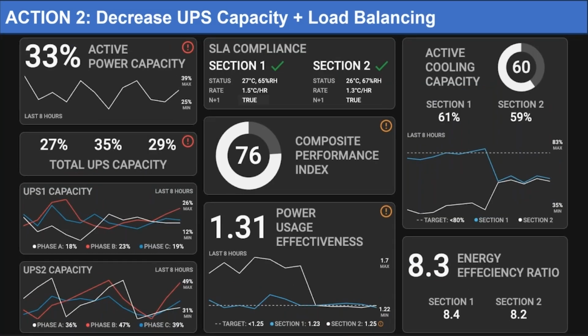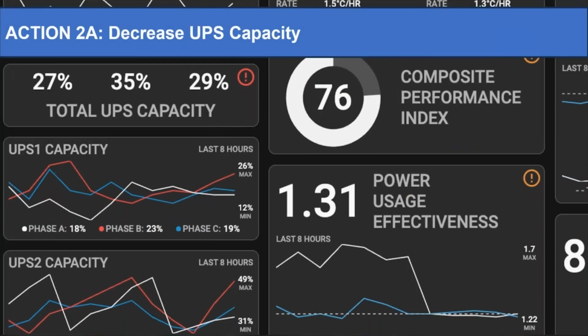The other step I'm going to take is decreasing my UPS capacity and my load balancing. Normally, you don't use this kind of dashboard to decrease the capacity of your UPS, but you normally use modular UPSs, and you're going to make sure that your UPS size equals the load you have. In this example, we're using a modular UPS, so we're going to detach some modules. In that case, we're going to decrease the UPS capacity. So we just switch down some of those modules and do not use the batteries anymore.